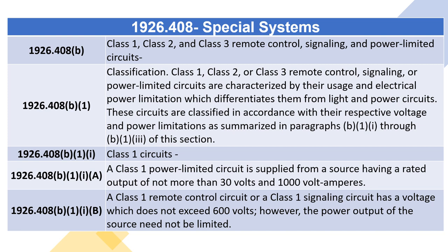1926.408(B)(1)(i) — Class I Circuits. (A) A Class I Power Limited Circuit is supplied from a source having a rated output of not more than 30 volts and 1,000 volt-amperes. (B) A Class I Remote Control Circuit or a Class I Signaling Circuit has a voltage which does not exceed 600 volts; however, the power output of the source need not be limited.